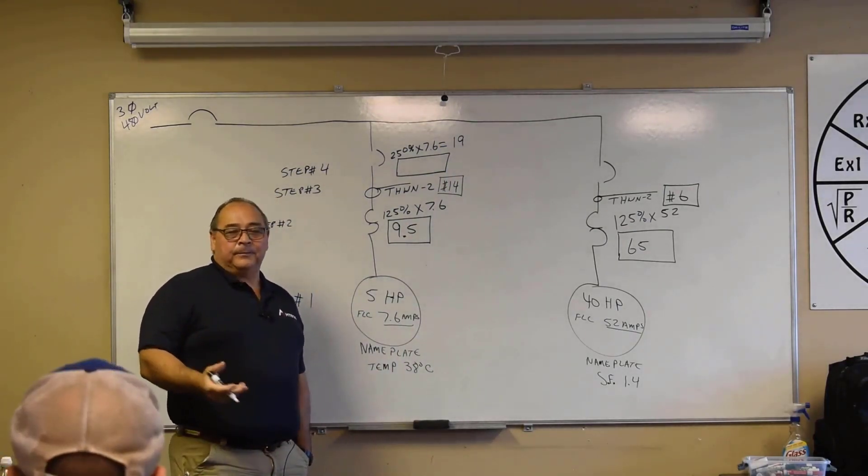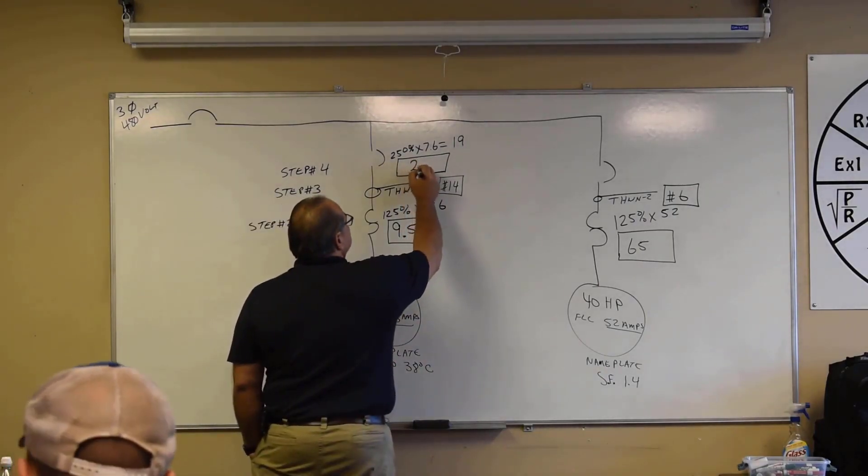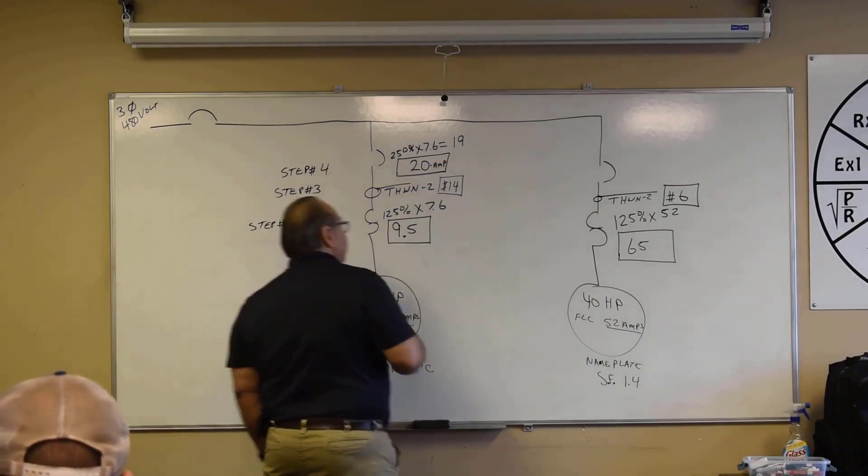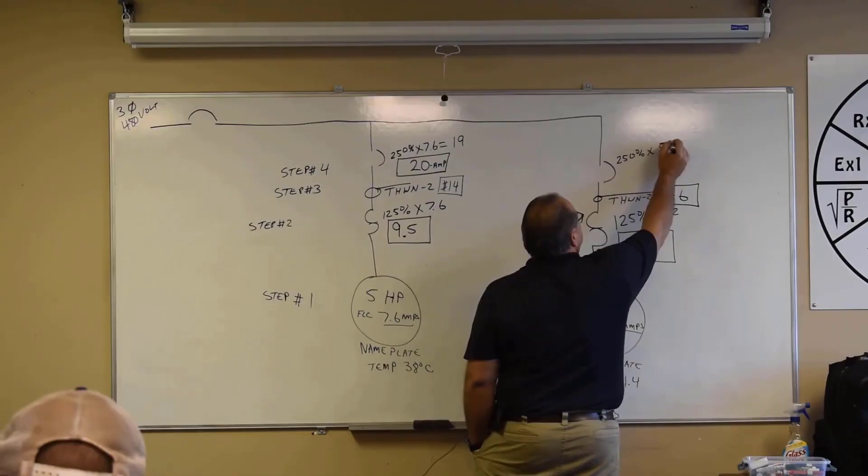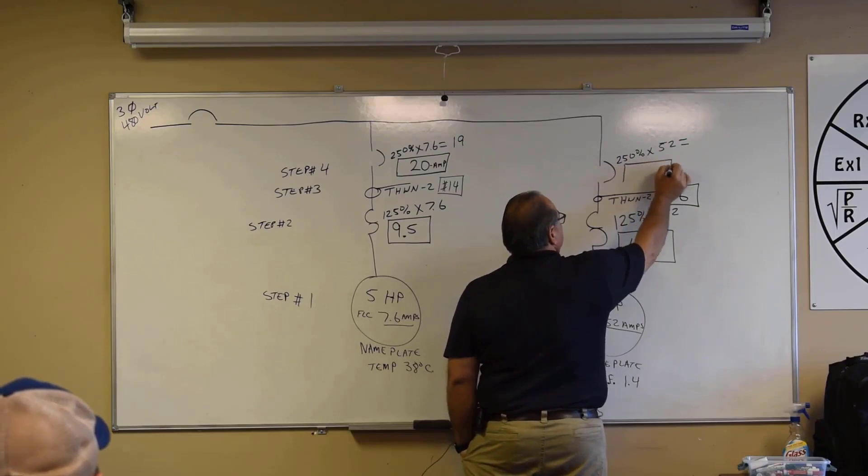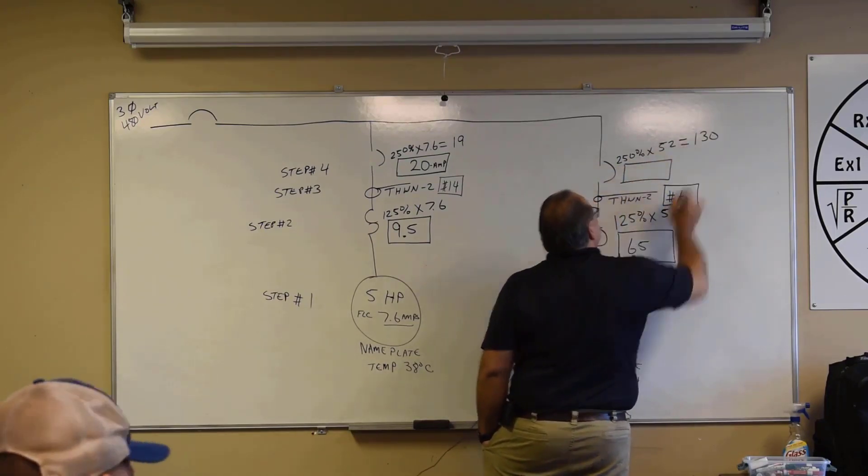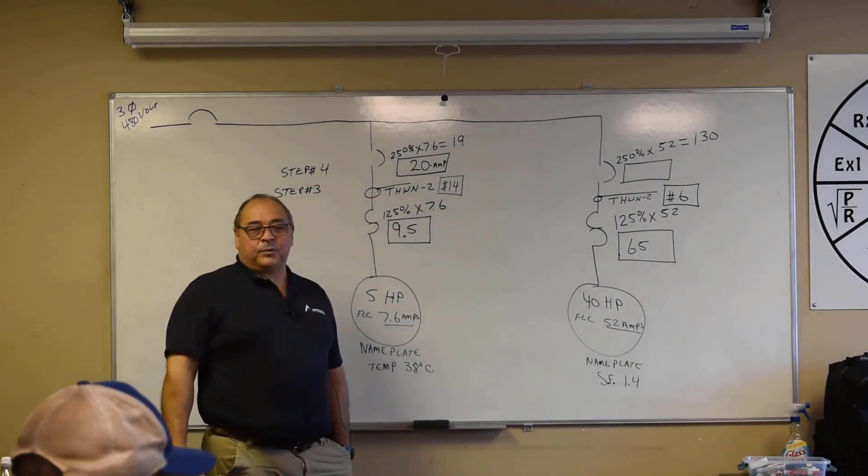Go to the next size up, which is 20 amps. Okay, over here we're going to be using that 250 percent again. We're going to multiply that times our full load current, 52 amps, right? What's that equal? 130, even. There's 130, not a standard fuse or circuit breaker size. So what we're going to do? Go to 150 amps.